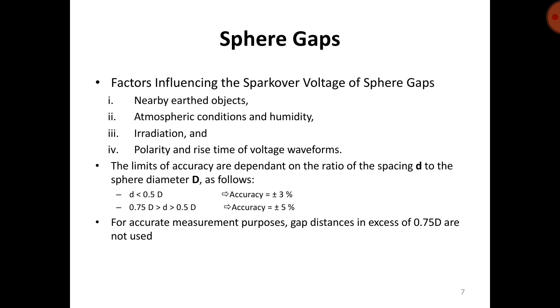The limits of accuracy depend on the ratio of the spacing d to the sphere diameter D as follows. If the spacing d is less than 0.5 × diameter D, then accuracy will be plus or minus 3%. If the spacing d is between 0.5 D and 0.75 D, it means spacing is in between 0.5 × diameter and 0.75 × diameter, then accuracy will be plus or minus 5%. For accurate measurement purposes, gap distances in excess of 0.75 D are not used. So these are the guidelines for spacing.